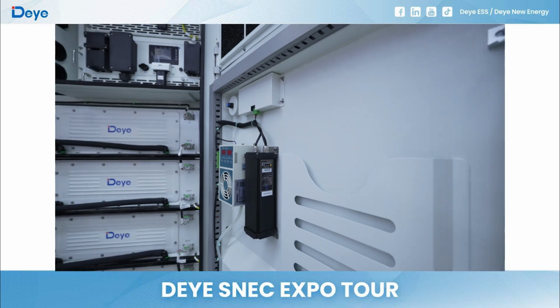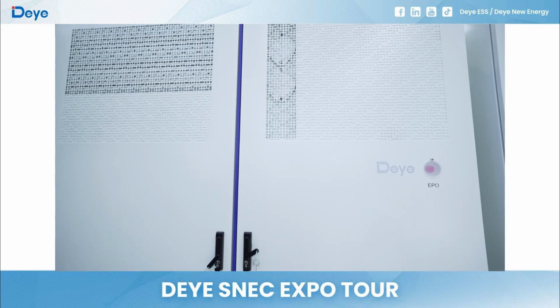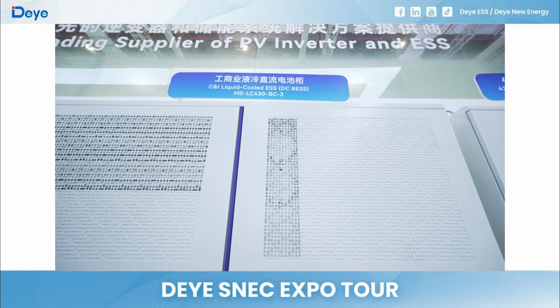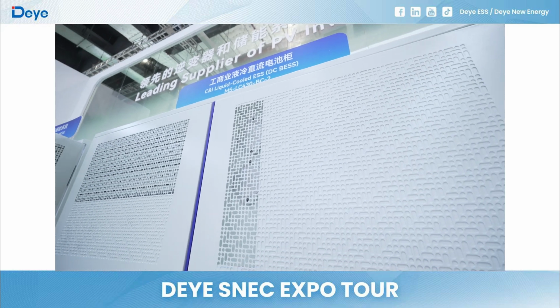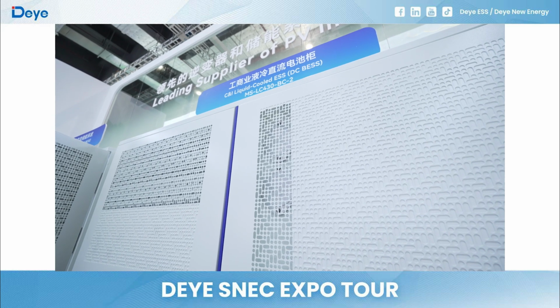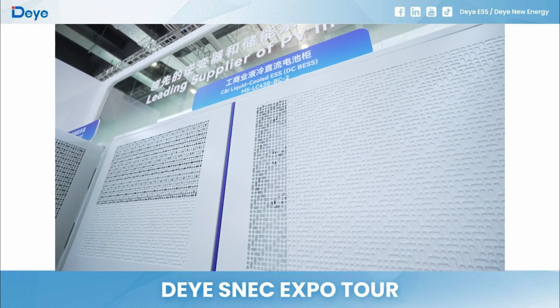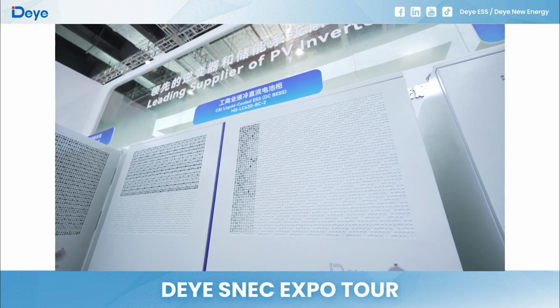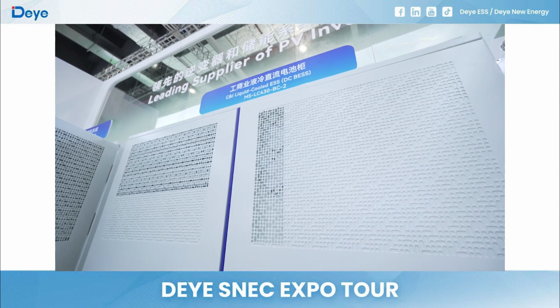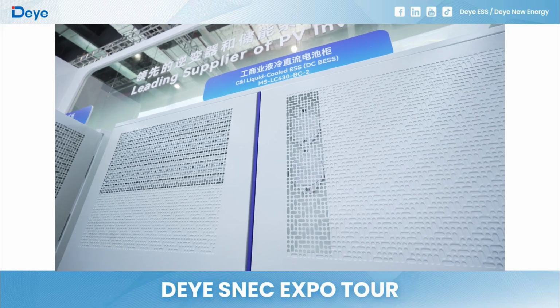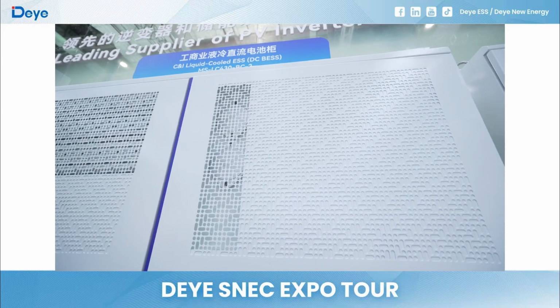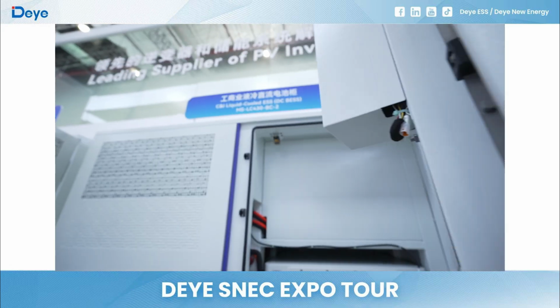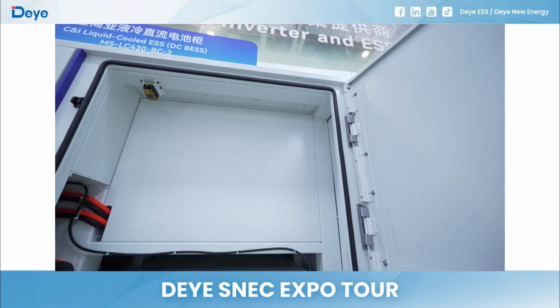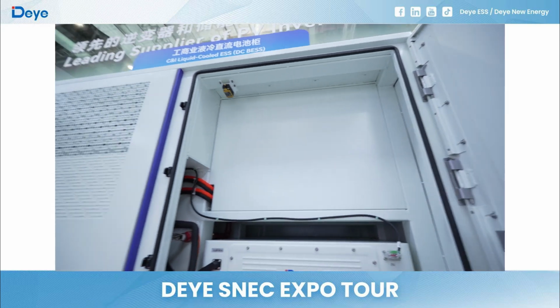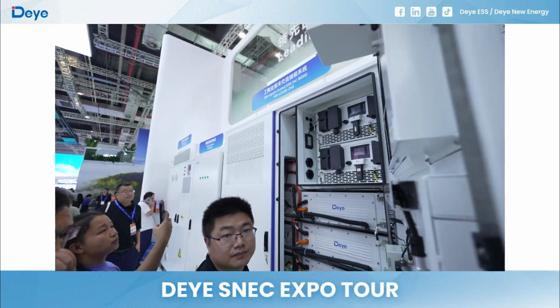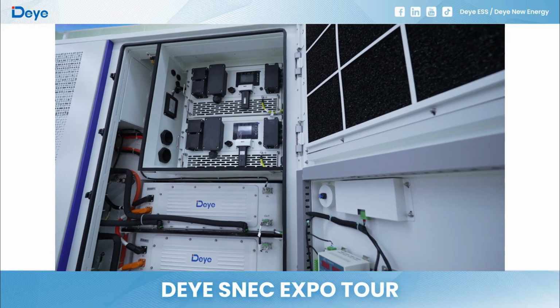And for the DC side expansion, it can also do DC side expansion. We can see this cabinet, the C&I liquid cooling ESS MS-LC430-BC2. Inside this cabinet, it only has the battery system, the liquid cooling device, and some firefighting system. We deleted the PCS module inside this cabinet, so this is just a DC cabinet. It's only a DC cabinet to do the expansion with the AC cabinet. Each AC cabinet can connect with 3 DC cabinets to do the expansion to meet 2 to 8 hours application.